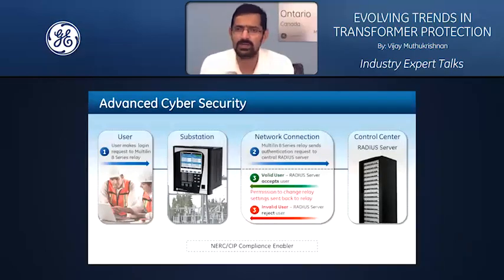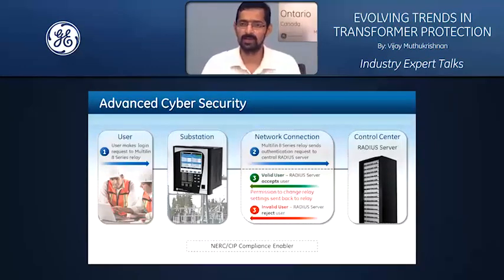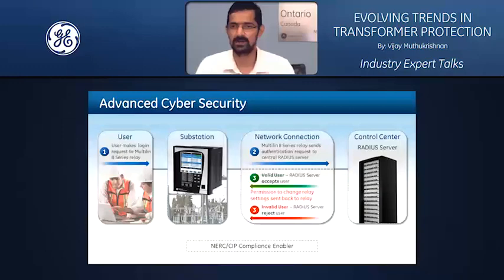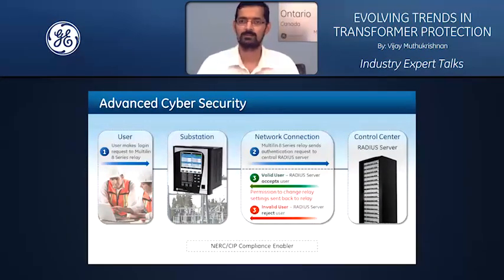And digging a little deeper into one functionality on the 845, which is related to the advanced security. What I'm showing here is the remote authentication functionality that the 845 relay offers. The remote authentication is achieved through having a centralized RADIUS server located in a control center. Now you have a relay deployed in a substation. A local user connects to the relay and says, here is my username, this is my role, and this is my password. The relay will immediately pass that user's credentials on to the RADIUS server and wait for feedback from the RADIUS server. When the RADIUS server tells the relay, yes, I recognize the user and the password, the relay will determine, okay, I'm going to let this individual access me.